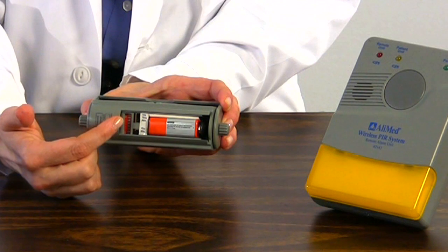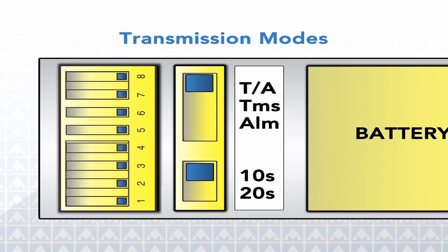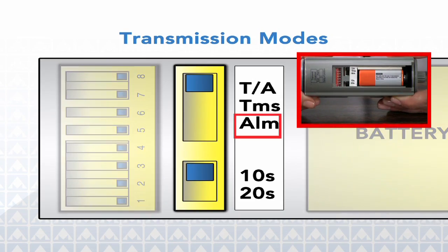Three choices can be made from the transmission mode using this selector switch. Choose alarm if you want only the alarm to sound with no signal sent to the remote receiver. Use this mode when using the PIR alarm alone.